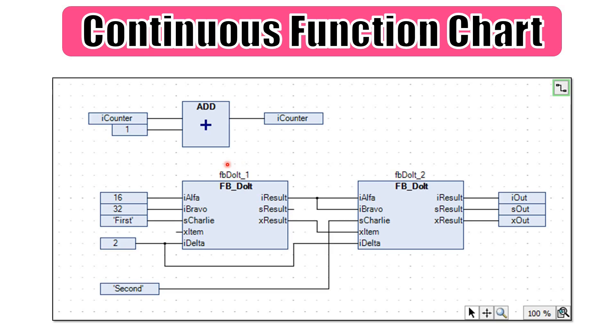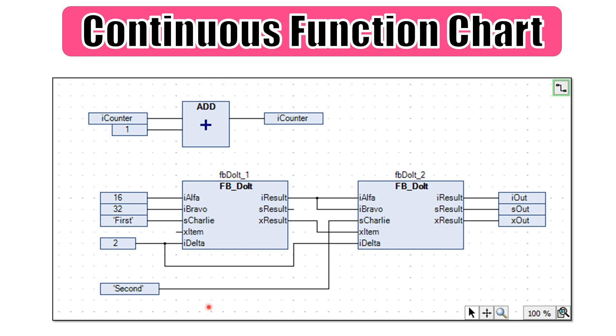And finally, regarding the continuous function chart, the execution order might be a little bit different. Because here you have the freedom in terms of placing the networks. So each one of these is indeed a network in any place in the editor. You can move them around. And by default, the execution order is similar to what we have with the FBD. So from left to the right and from top to bottom. Therefore, the execution order considers the data flow and the topological location of the network. However, there is an option to change this and prioritize the execution of a given block or set the execution order manually.